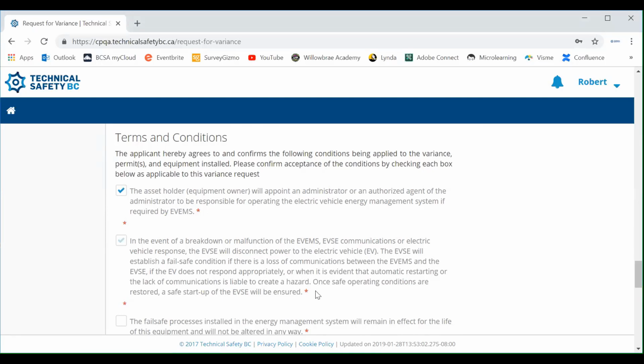In the event of a breakdown or malfunction of the EVEMS, EVSE communications, or electric vehicle response, the EVSE will disconnect power to the electric vehicle. The EVSE will establish a fail-safe condition if there's a loss of communications between the EVEMS and EVSE. If the EV does not respond appropriately, or when it's evident that automatic restarting or lack of communication is liable to create a hazard, once safe operating conditions are restored, a safe startup of the EVSE will be ensured. We're definitely going to want to make sure we've looked at that and are able to click that box.